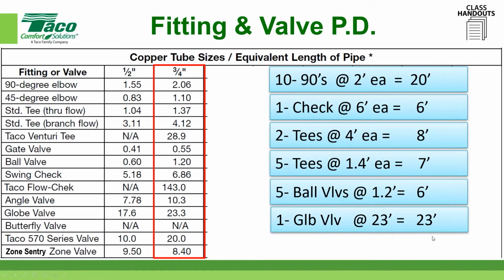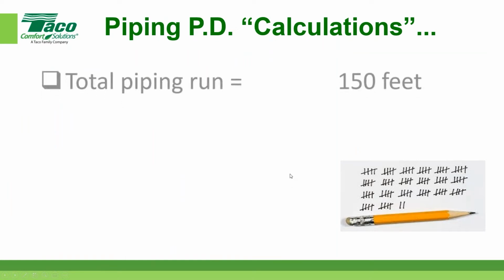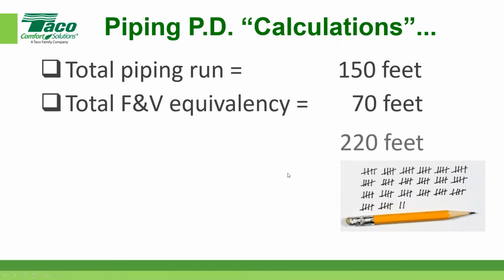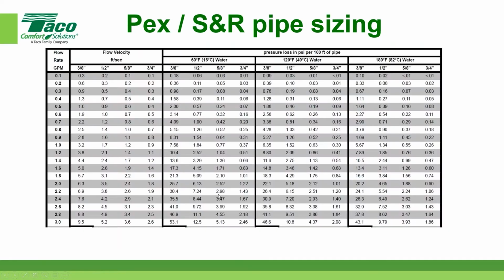Anyway, I add all this stuff up in there, and I get a total fittings equivalency of 70 feet of additional straight pipe. So that's where people lose this whole equivalency thing. They can't get their arms around it. It's just as if we had 70 more foot on that 150-foot run like I'm showing you here. So we're still roughly what we were using, the valve and fitting factor, but with some difference. And this is what the difference is.